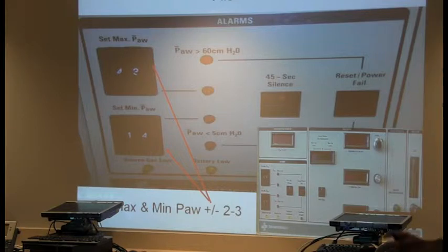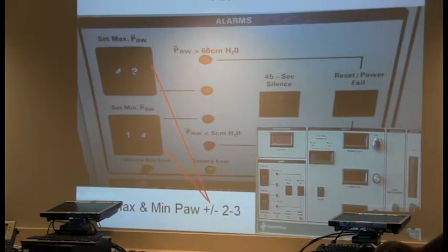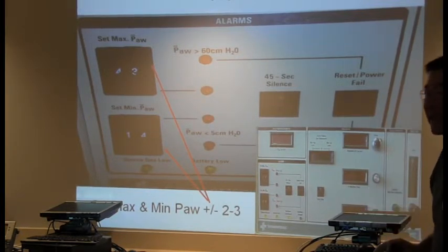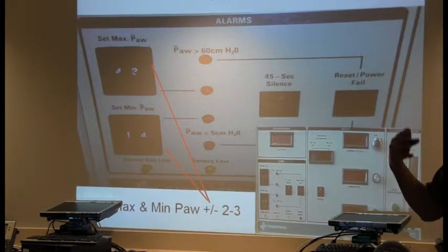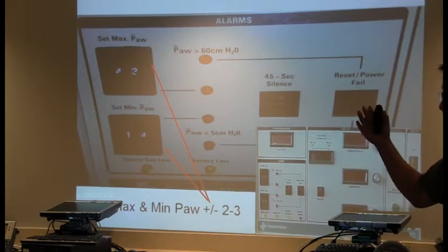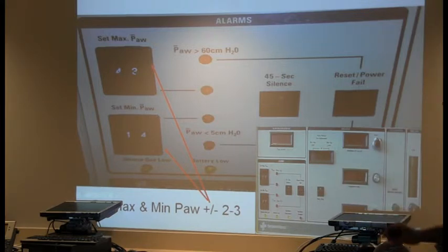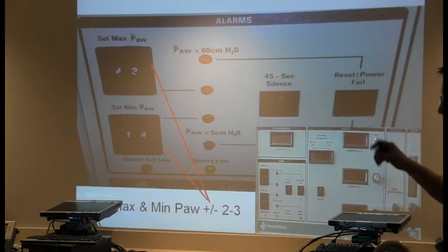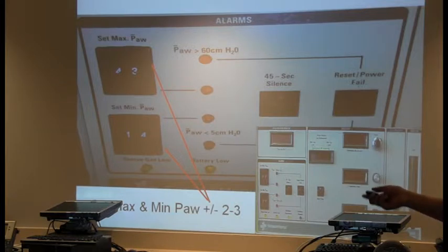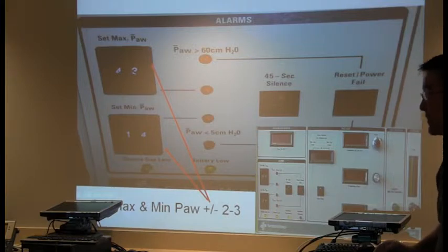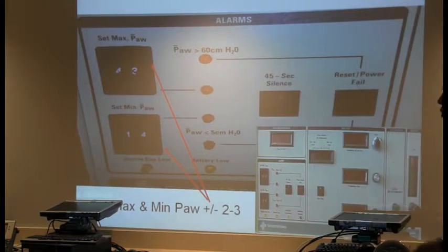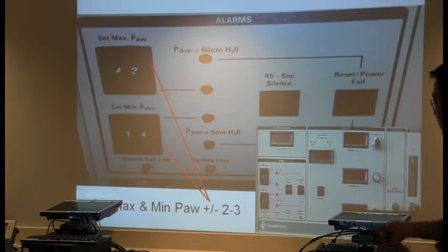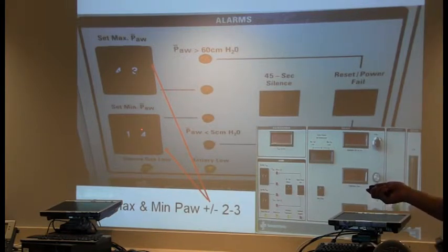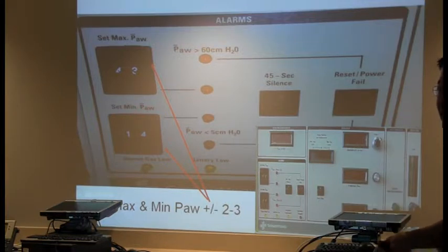No. Okay. So this was a big question that I have for people, that this is an alarm. This is not like a conventional ventilator where we set a high pressure alarm. So when the peak pressure hits that point, the vent shuts off automatically. Well, this doesn't function that way. This is just a basic alarm. If our mean hits above 42 or 43, it's going to alarm at you. But the vent will not shut off. Okay? Understand that. And I'll show you the other way we can show you how to safely set your pressure limit. Okay, minimum. If your mean airway pressure falls below 14, again, it's going to chirp.